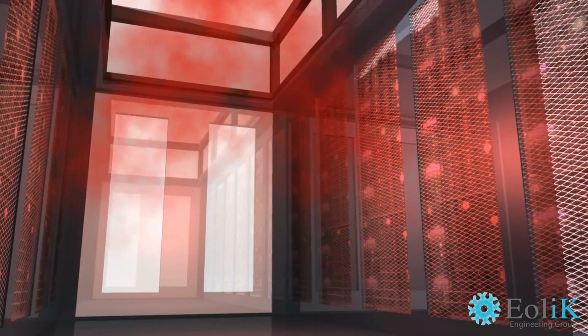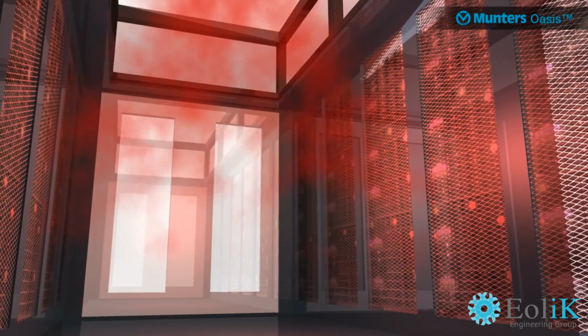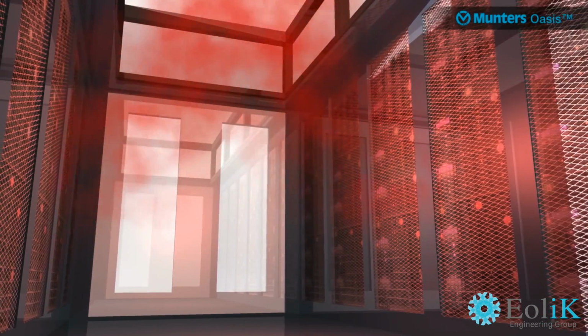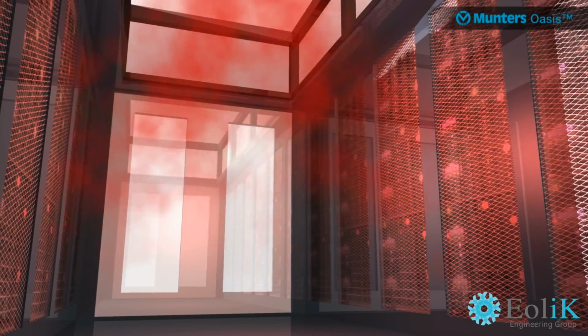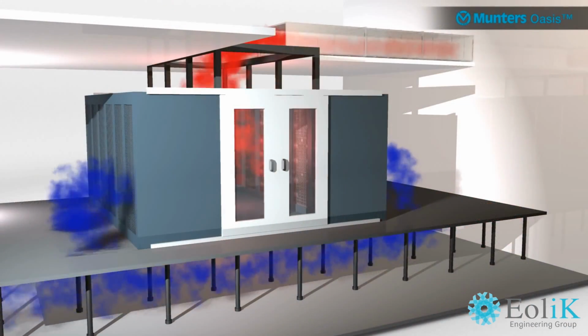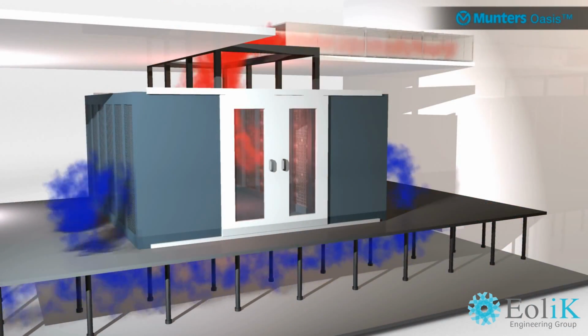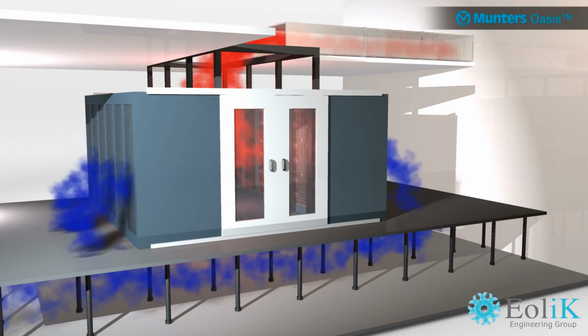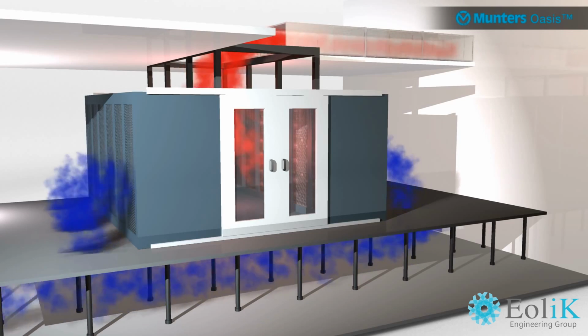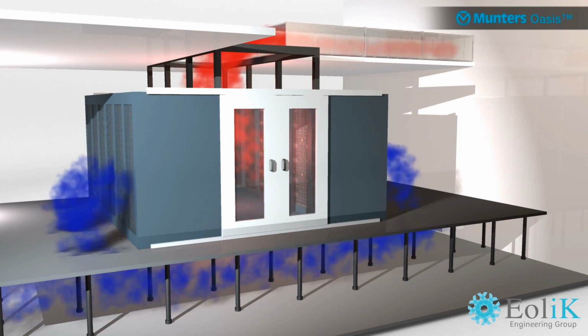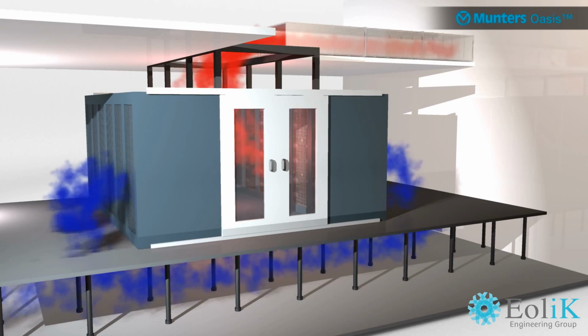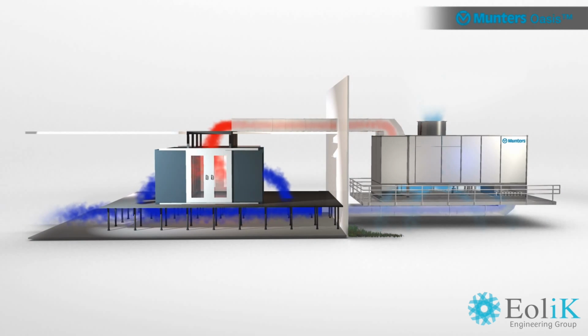Hot aisle containment allows the immediate containment and removal of the server exhaust hot air and prevents its entry to the remaining areas of the data center. The allowable server air inlet temperature increase means that airside economization is more widely applied. Here we explain why Munters Oasis innovative system is up to 75% more energy efficient than standard air conditioning systems. Cold outside air can help cool the hot air inside.